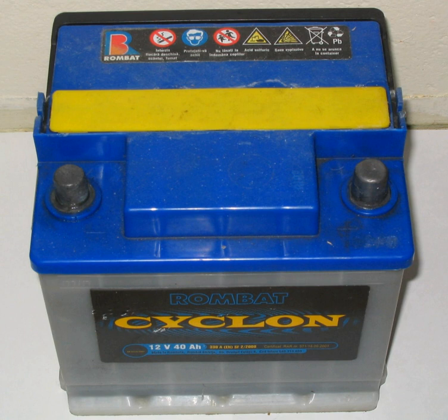A typical lead-acid battery contains a mixture with varying concentrations of water and acid. Sulfuric acid has a higher density than water, which causes the acid formed at the plates during charging to flow downward and collect at the bottom of the battery. Eventually the mixture will again reach uniform composition by diffusion, but this is a very slow process. Repeated cycles of partial charging and discharging will increase stratification of the electrolyte, reducing the capacity and performance of the battery because the lack of acid on top limits plate activation. The stratification also promotes corrosion on the upper half of the plates and sulfation at the bottom.